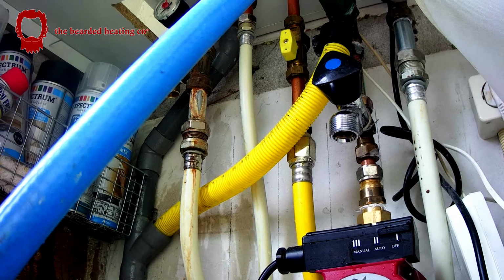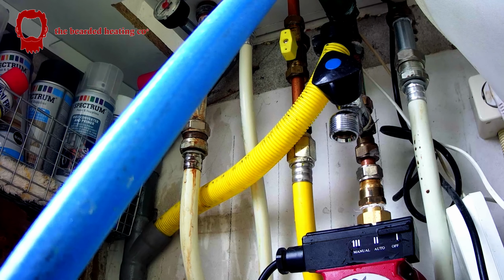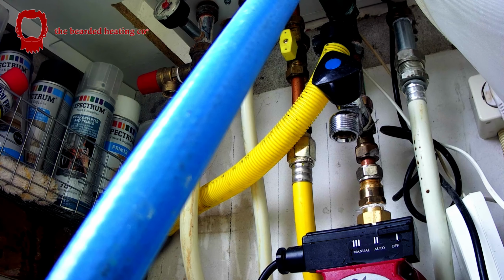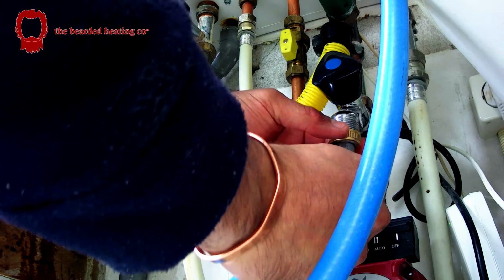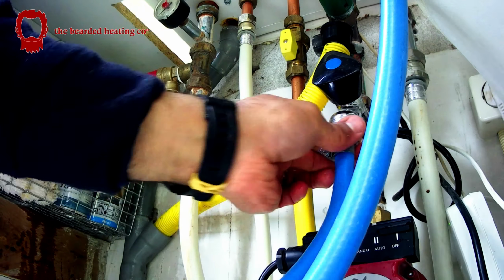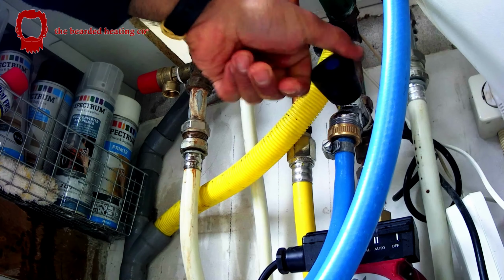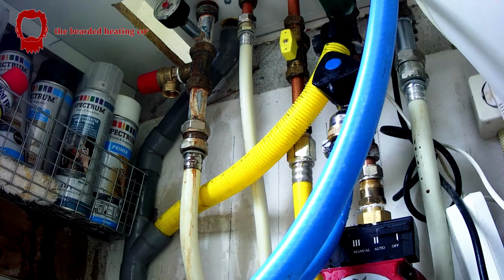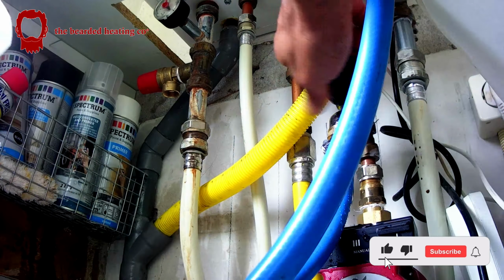And now I want to just check the pressure on the expansion vessel whilst it's drained down. Using my trusty Milwaukee air pump. Expansion is at 0.6 bar, which is not too bad. I'll just recharge it to 1 bar. Right, we're good there. Expansion vessel's recharged and done. And then pressurize the boiler. That's it, pressurized and done.